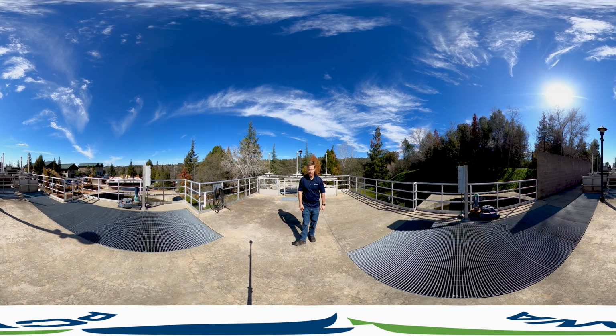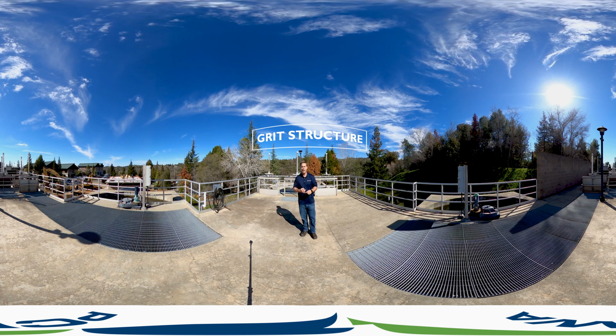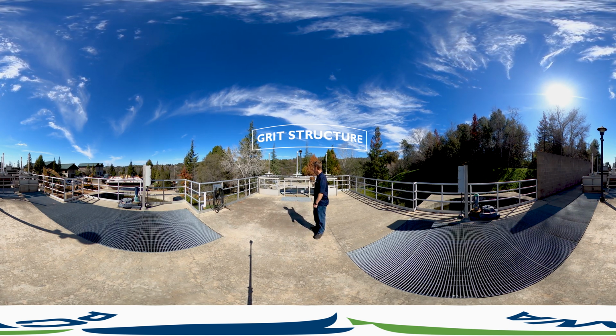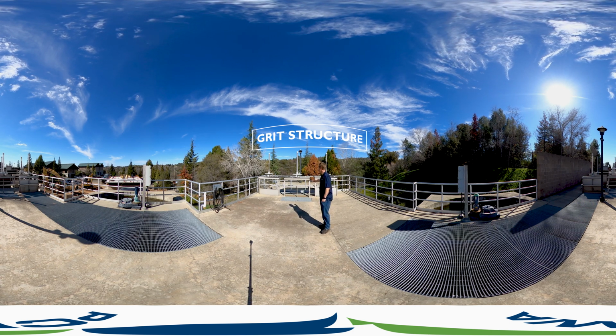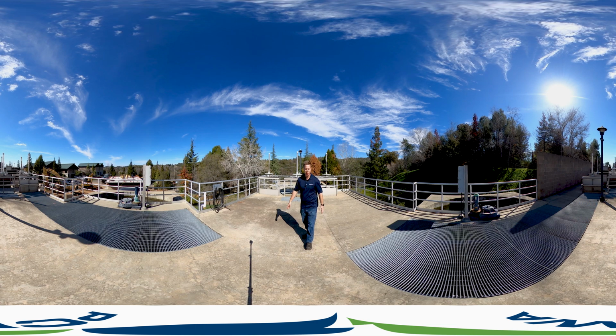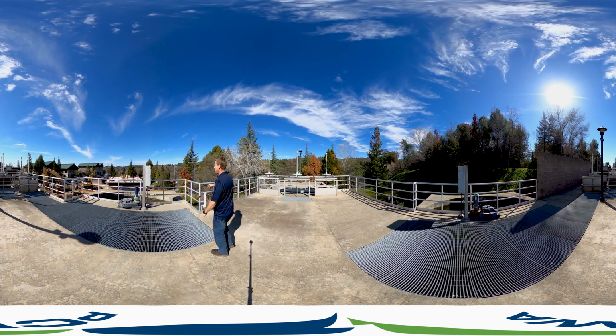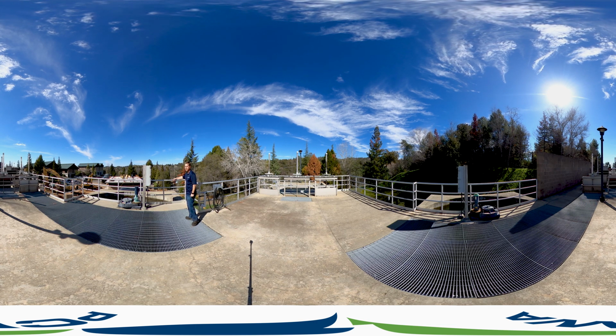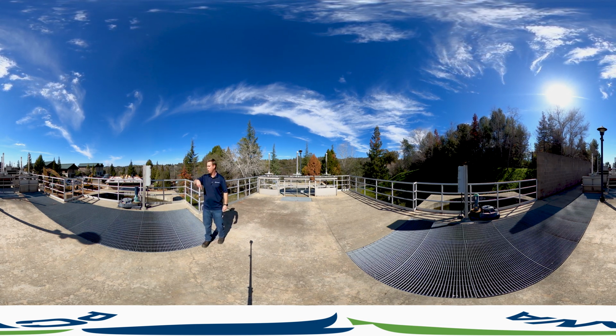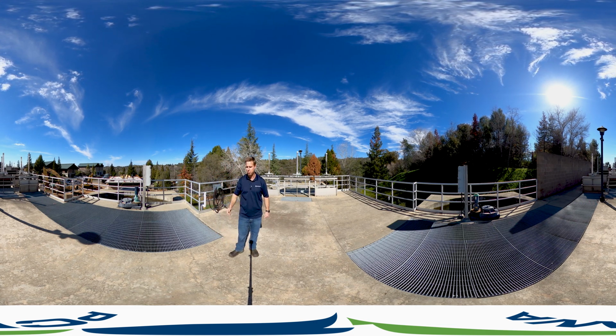So here we are in the grit structure. A grit structure is primarily designed to remove any sand, small pebbles, sticks, leaves that flow into this process. If you look behind me, you see this water bubbling over. This is the inlet to the grit structure. That water then flows underneath me to these two sides. If you follow me to this side, you'll see that the water is creating a vortex in here. There's a paddle shaft mixer that's vertically spinning that water to help any of the heavier objects settle out before it moves on through the process.